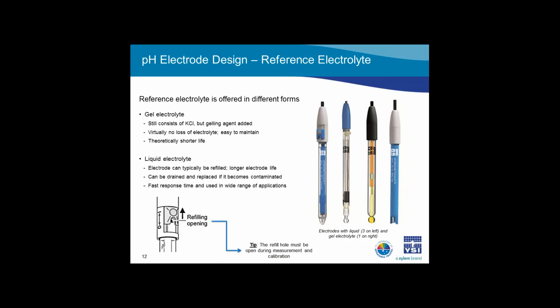Electrodes with liquid electrolyte can usually be refilled. This results in a longer electrode life. It also allows the user to easily refill the electrode when needed, as well as replace the electrolyte if it does become contaminated. Response time of the electrode is typically faster, and the measurement signal is more stable if liquid electrolyte is used. Faster electrolyte outflow from these electrodes also helps to reduce troublesome diffusion potentials that may develop, and it also ensures the electrode junction doesn't become easily clogged.